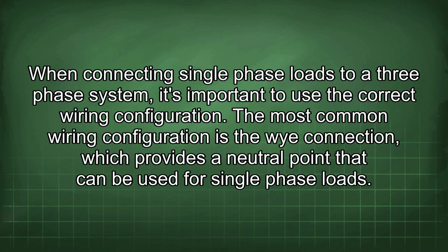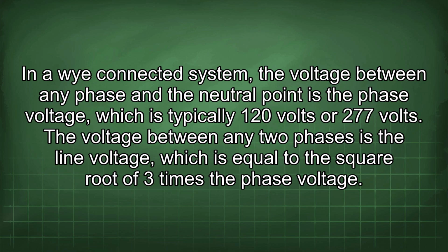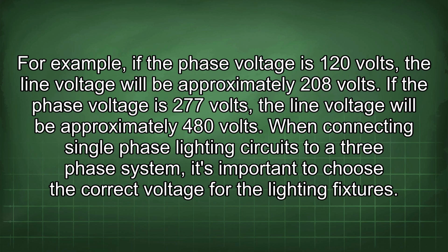The most common wiring configuration is the Y connection, which provides a neutral point that can be used for single-phase loads. In a Y-connected system, the voltage between any phase and the neutral point is the phase voltage, which is typically 120 volts or 277 volts. The voltage between any two phases is the line voltage, which is equal to the square root of 3 times the phase voltage. For example, if the phase voltage is 120 volts, the line voltage will be approximately 208 volts. If the phase voltage is 277 volts, the line voltage will be approximately 480 volts.